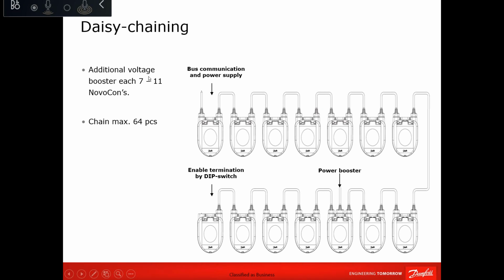And the power booster, in our example here, we're putting 7 to 11, but you can also see from the local LEDs where you need to boost the power. Or if you have the BMS, you can see that you have an error or an alarm about abnormal power supply. There you need to go and boost the power, which will save you something. But in the projects we have done here, in most cases, every Novocon, they are providing the power for it locally from every controller to the actuator, because they need to use the local controls.